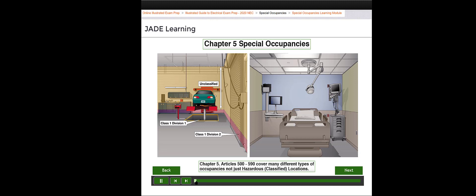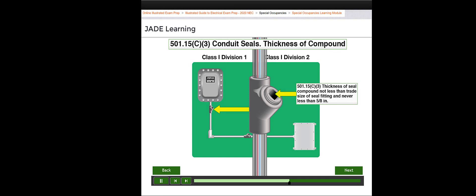This includes occupancies that may be classified as hazardous because of the presence of flammable or combustible gases or vapors, combustible dust, or fibers. Seal fittings must not be less than the trade size of the seal fitting, but is never permitted to be less than five-eighths inches thick, unless specifically identified for a higher rating.